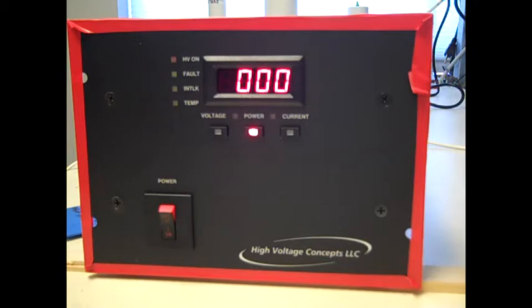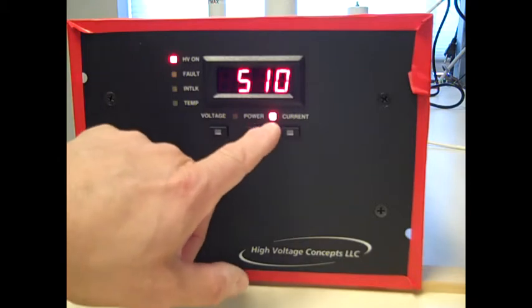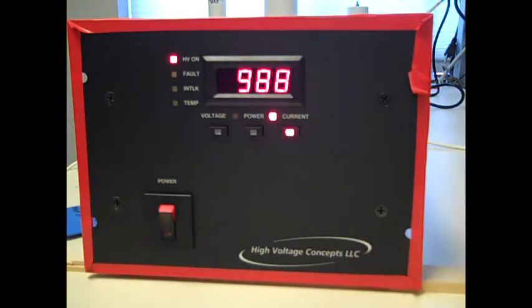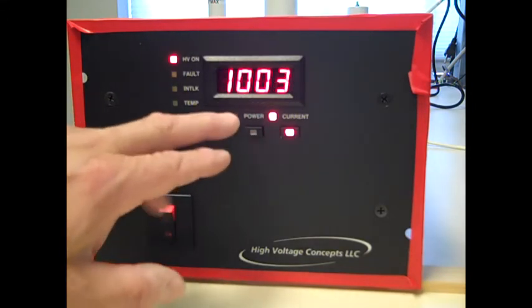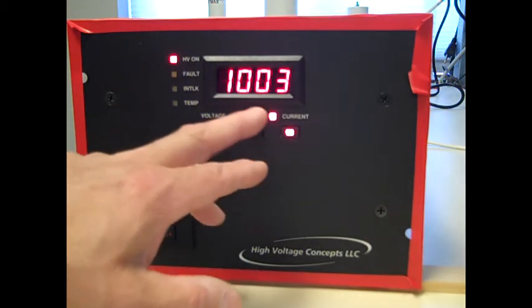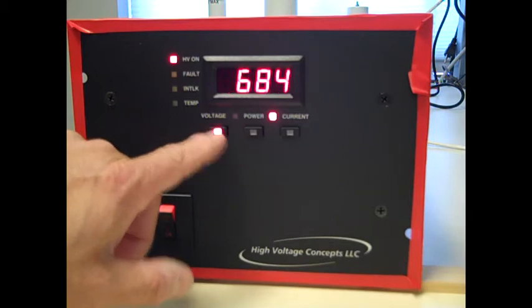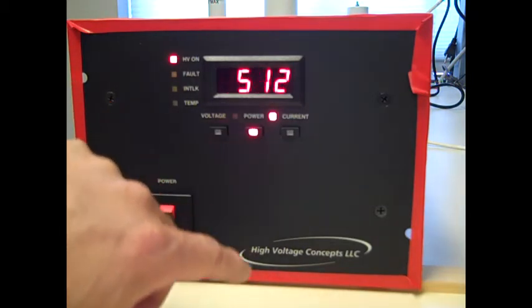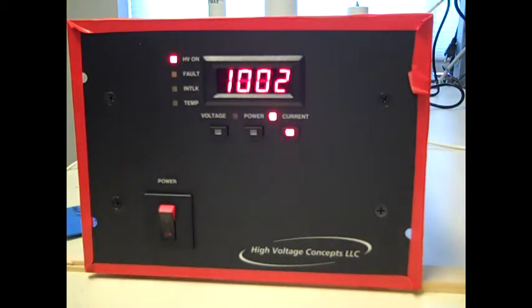Okay, we're back. Now we applied a much heavier load that would not allow the power regulator to work even if we were asking for it, and not allow the voltage regulator to be in control even though we were asking for it. So we're going to go ahead and turn high voltage on, and you're going to see there's only 500 watts being output, but it's in the current regulation mode. Why? Let's push the current button, because we have 1000 milliamps, 1 amp. So even though you're in the power mode, you've hit the current regulator limit, and that will be in control. Let's look at the voltage. We're at 509, 511 watts, and 1 amp.